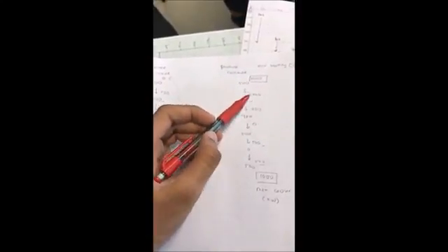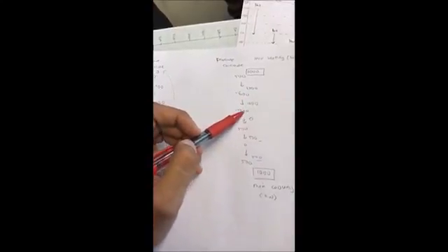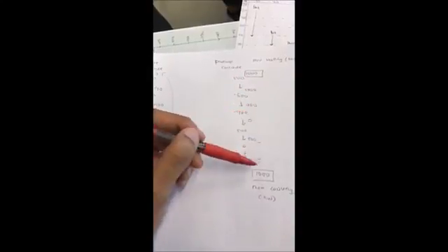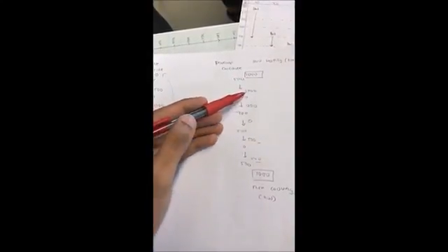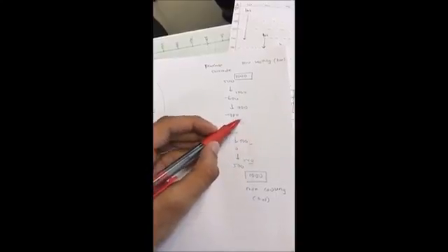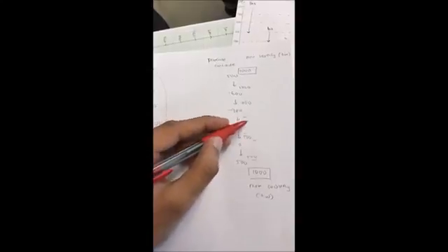So you begin with 1000, and then you just follow the same process. So 1000 plus 500 is 1500, minus 600 is 900, etc. You'll notice that when you complete this, there are two observations. First of all, you should not find any negative sign, meaning no deficit after you've done your feasible cascade. And the next thing is that you should find a point where the remainder energy is 0. At this point, you will find your pinch temperature.